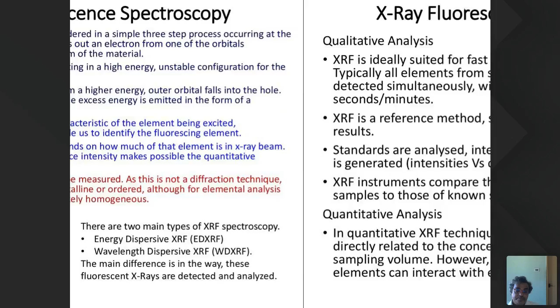XRF is used mostly for qualitative as well as quantitative analysis. In the case of qualitative analysis, typically elements from sodium through uranium can be detected simultaneously, with good quality spectra obtained in a very short time. Also, it can generate reference standards for quantitative results.